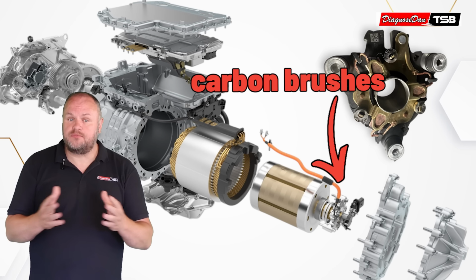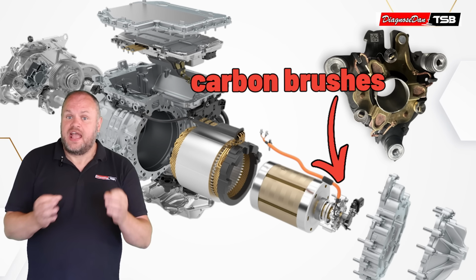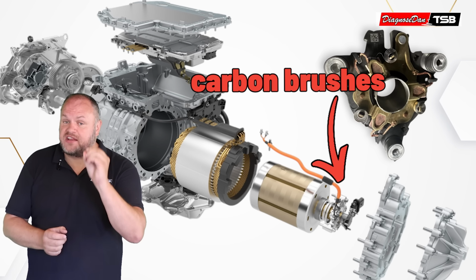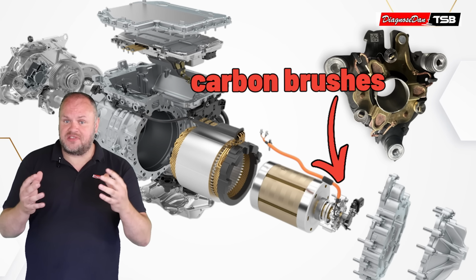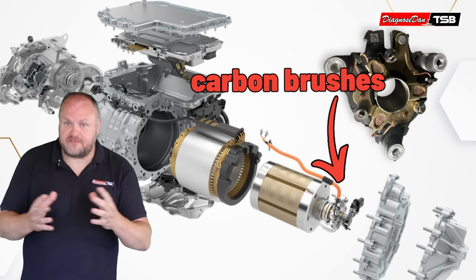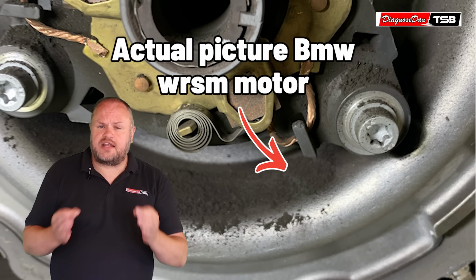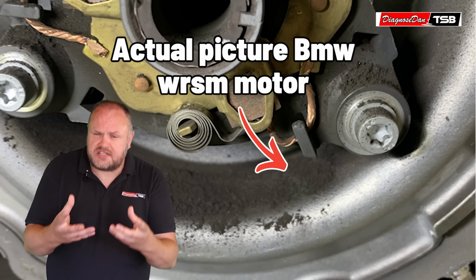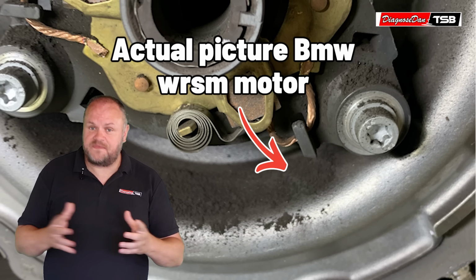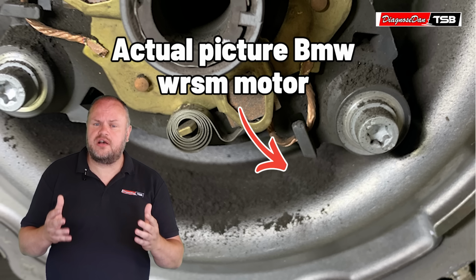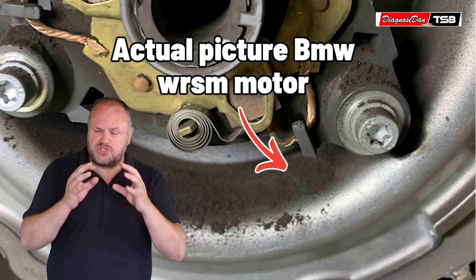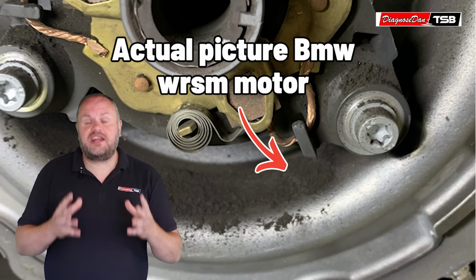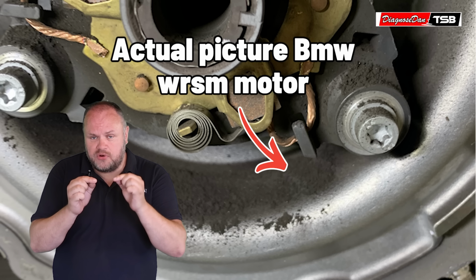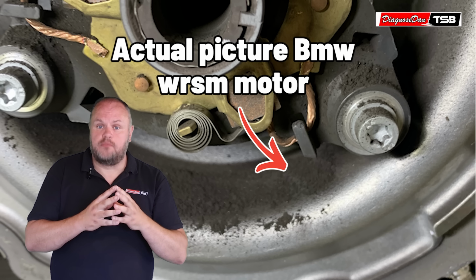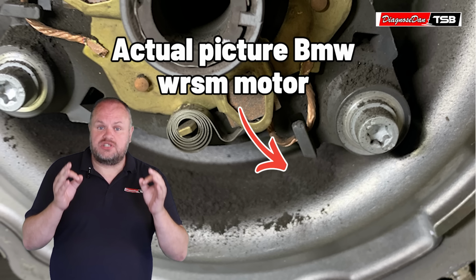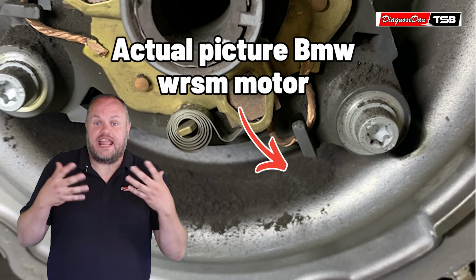As we all know, carbon brushes wear out over time, and this produces very fine carbon dust, and this carbon dust is electrically conductive. You can probably understand that having conductive carbon dust inside a high voltage environment is not desirable, because if enough carbon dust builds up inside the motor, it can create a path between the high voltage components and the housing of the motor, and if this happens, the motor is no longer sufficiently insulated.